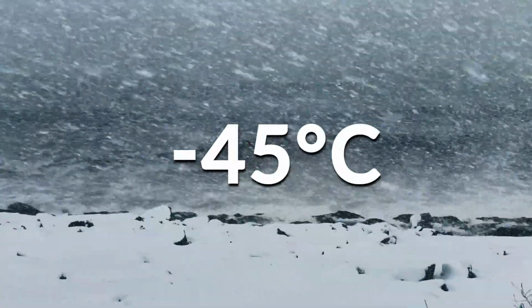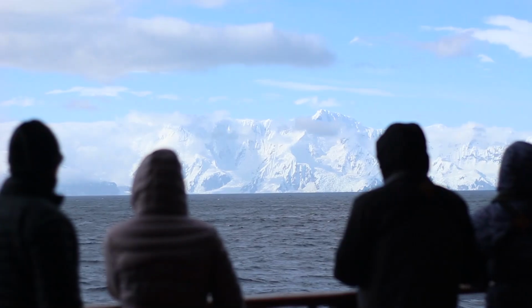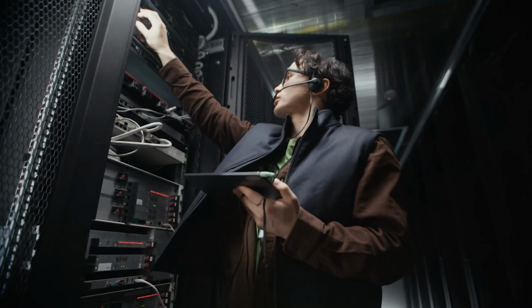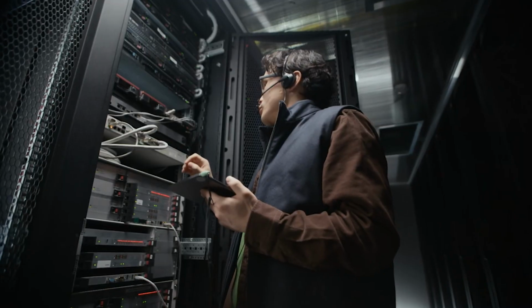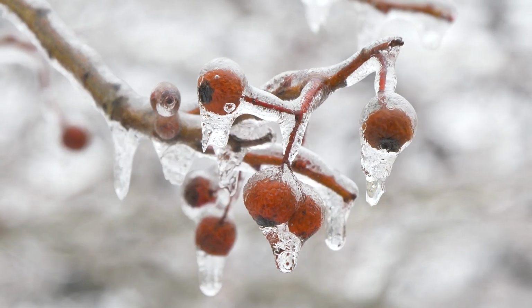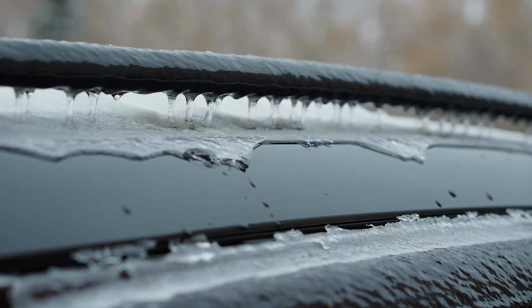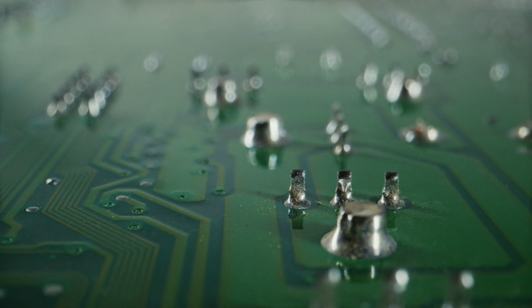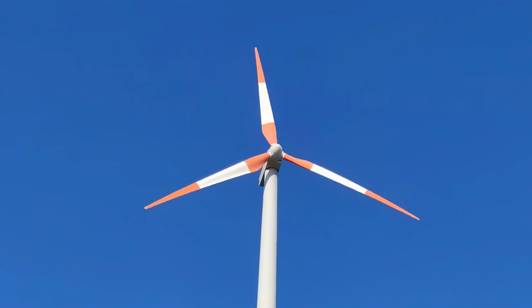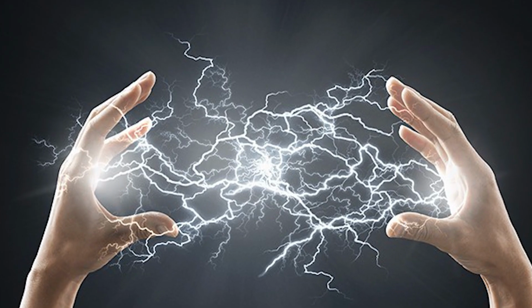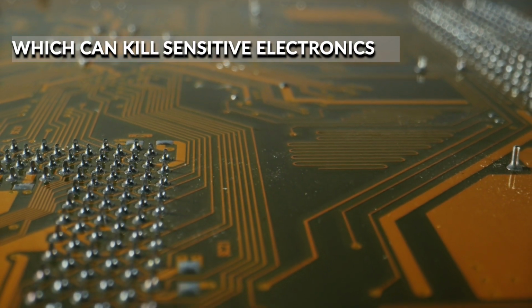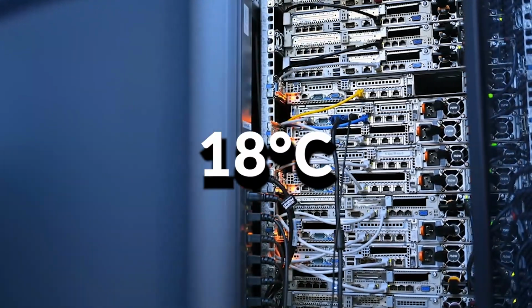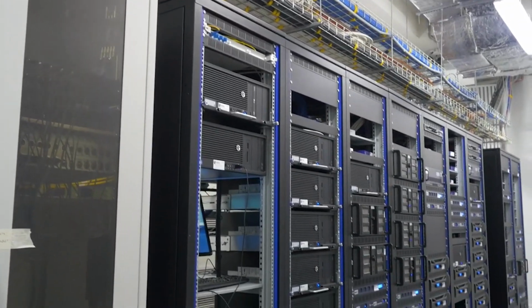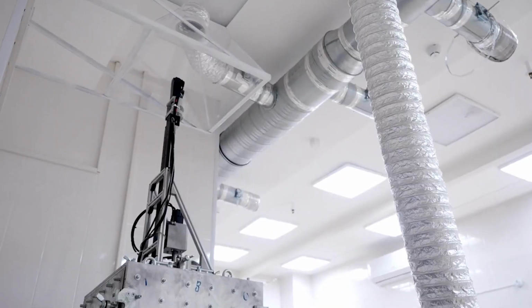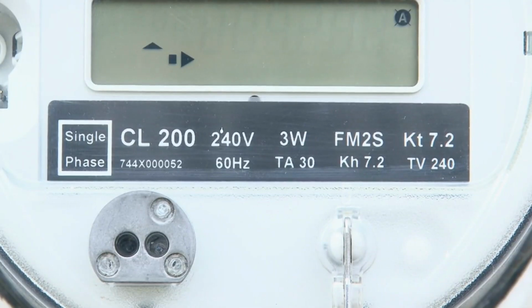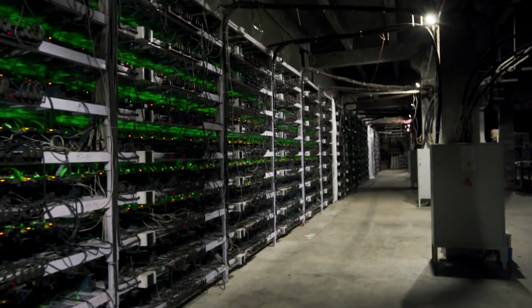But at minus 45 degrees Celsius, Antarctica's average temperature, not even its extreme, you've crossed into a completely different engineering problem. Moisture freezes on equipment, while extreme temperature differences cause metal to expand and contract, enough to crack solder joints and damage connectors. The dry polar air also generates far more static electricity, which can kill sensitive electronics. And to keep the facility at a stable 18 degrees Celsius, where servers operate reliably and condensation is avoided, you'd actually need to run heaters constantly, burning energy to fight the environment instead of benefiting from it.